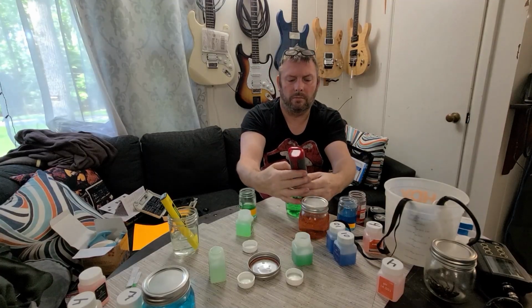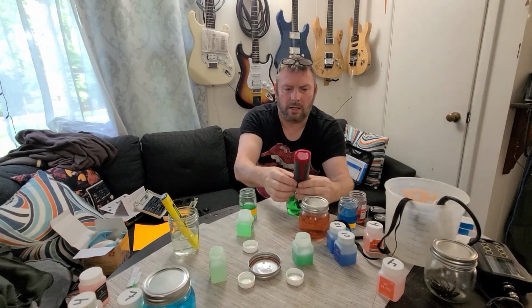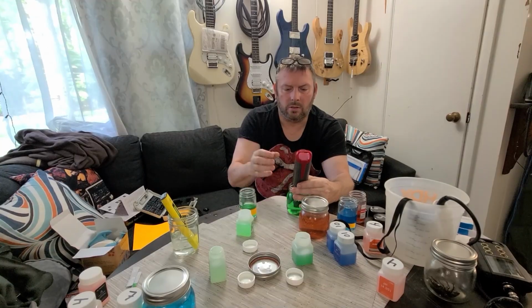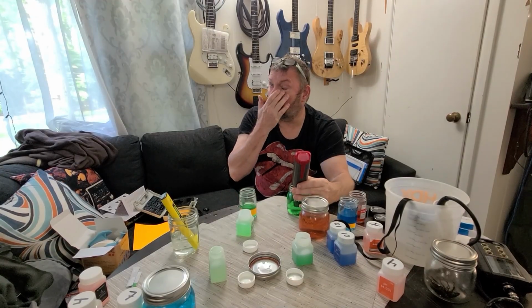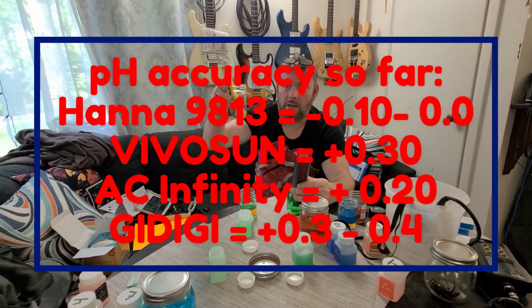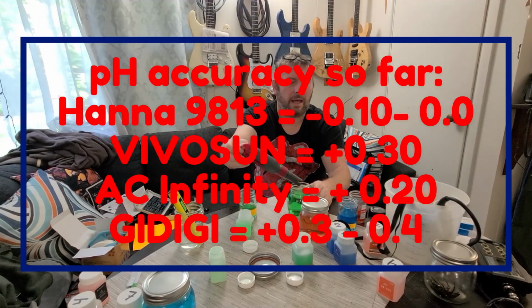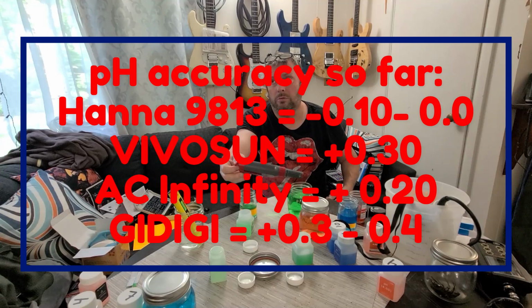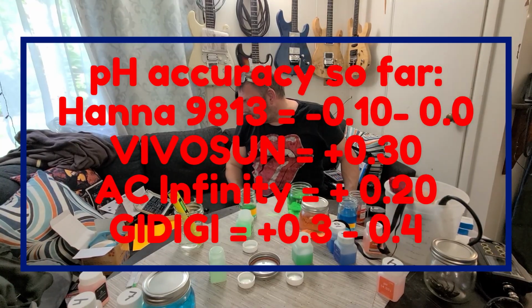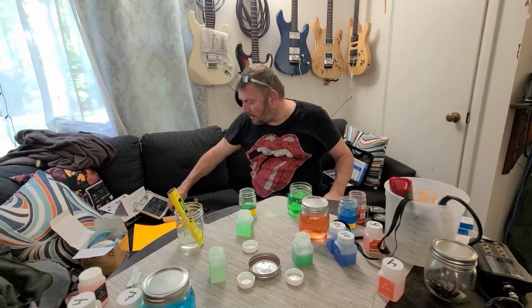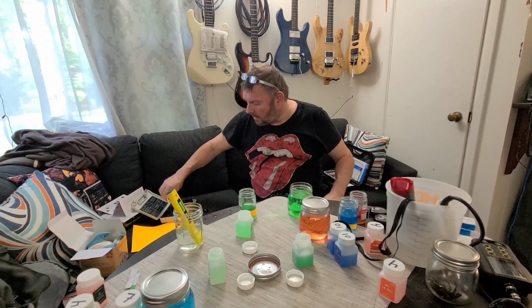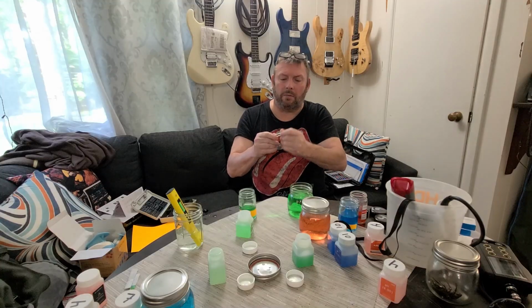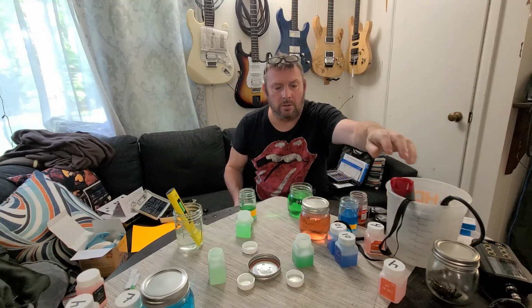Oh, that's kind of a bummer, because that means G-Digi, as much as I like G-Digi, 7.2, and it's supposed to be 6.8. So G-Digi and VivoSun are off by 0.3, so almost a third of a point, close to it. AC Infinity was off by 0.2, which is like a fifth of a point, right? And Hanna seemed to be more or less spot on. Kind of a bummer. I've got the little cleaning brush. I don't know. I mean, these meters are all new. Do I really have to go through this much trouble cleaning brand new meters? Maybe I do. I don't know.